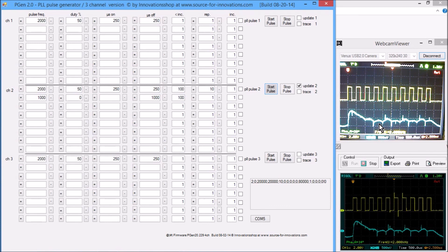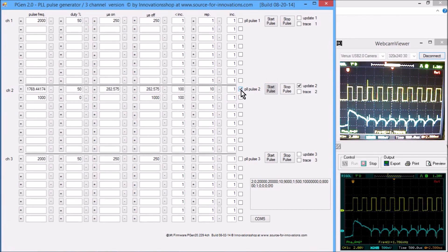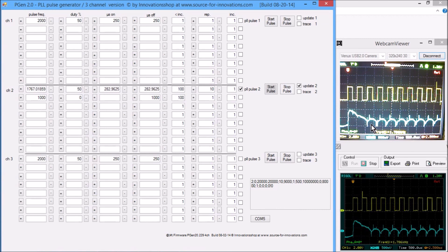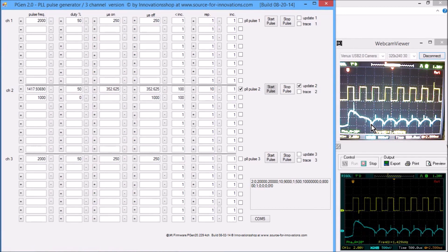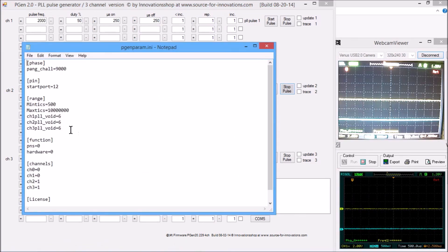These feedback signals change when the frequency changes due to PLL regulation. The distortion situation can be reduced by optimizing the feedback amplification circuit. There is a reason why clipping diodes are used. To avoid these disturbances there is an INI file where you can declare some pulses as void, so that PLL calculation starts at the seventh pulse in this case.